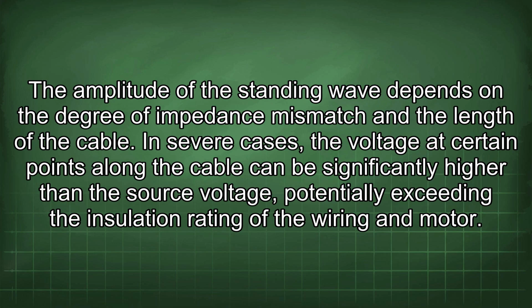The amplitude of the standing wave depends on the degree of impedance mismatch and the length of the cable. In severe cases, the voltage at certain points along the cable can be significantly higher than the source voltage, potentially exceeding the insulation rating of the wiring and motor.